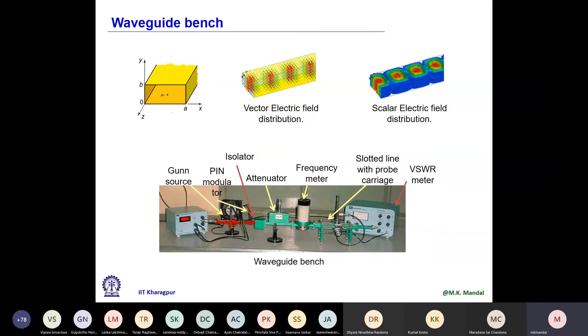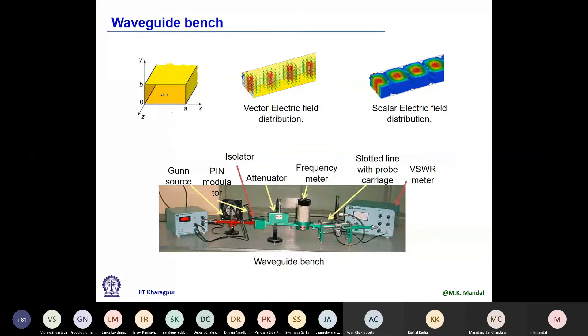Starting from the left-hand side, it begins with a microwave source. In our lab we have two different types of microwave sources: one is the Reflex Klystron, which is a tube-based device, and the second is a Gunn diode-based source. This source generates a continuous microwave signal in CW mode — like a sinusoidal signal generator — but the frequency is in the X-band gigahertz range. We can tune the frequency using a mechanical screw.